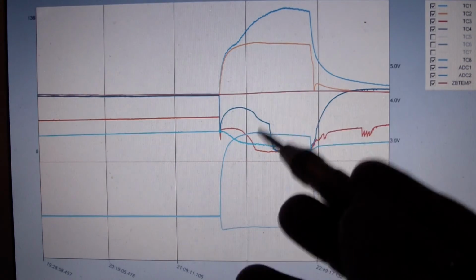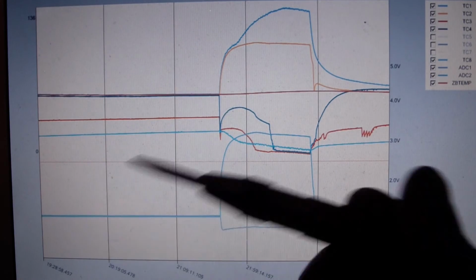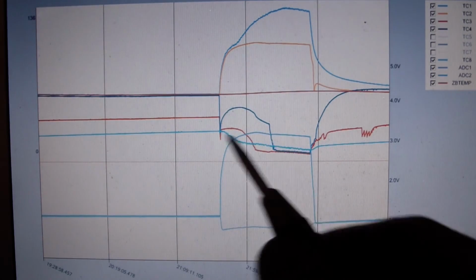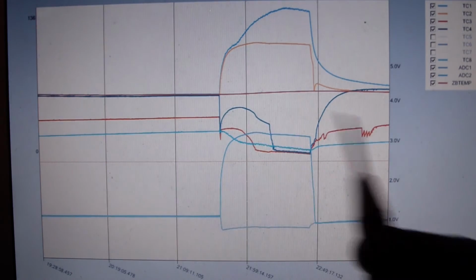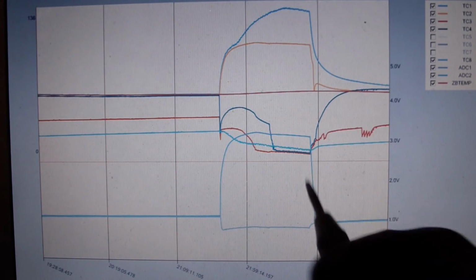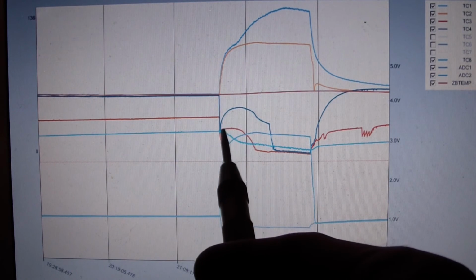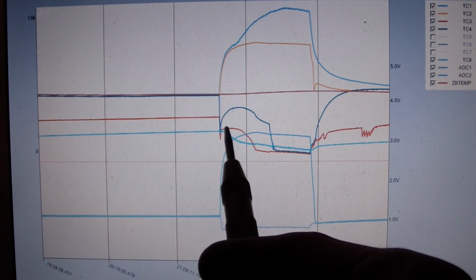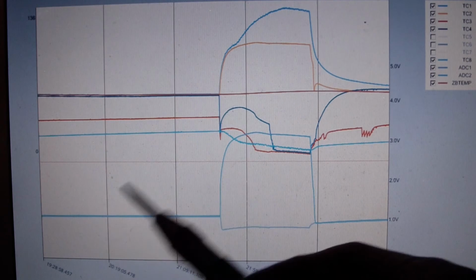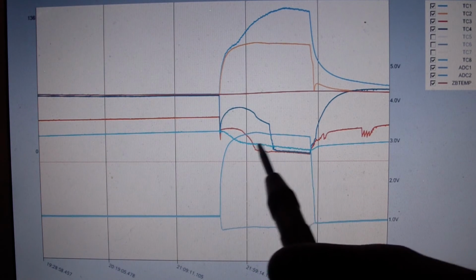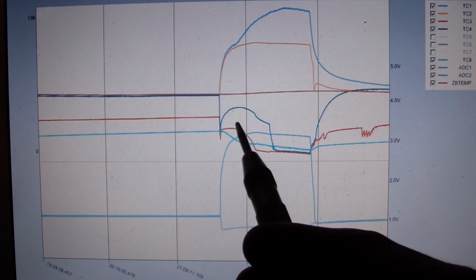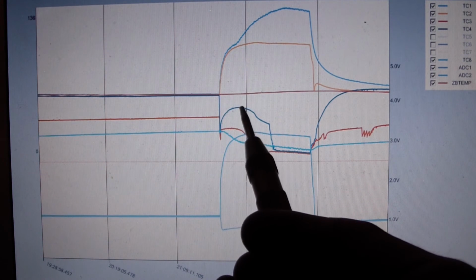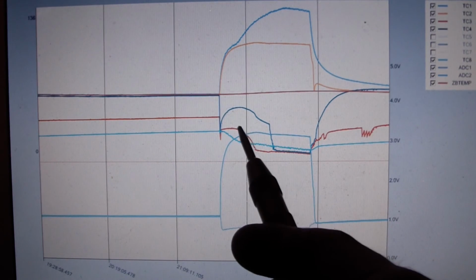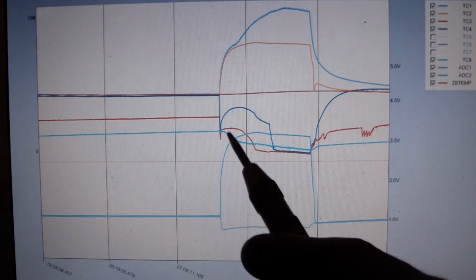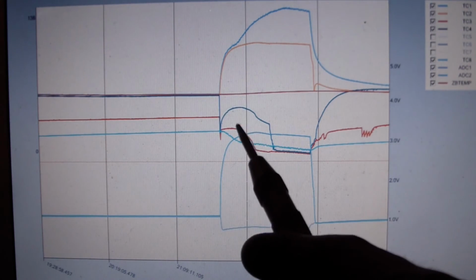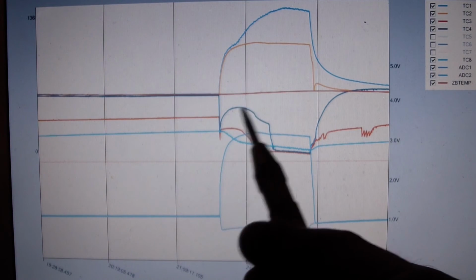In addition to that, I want to get better subcooling on the high side. So I need to add some more heat exchange area there, and possibly a receiver there, and balance these things together. Beyond that, when we first start up here, although we have still pretty high superheats right after the evaporator, this red line, relative to saturation temperature, which is pretty much where that's at right there. You can see that the superheated gas finally going to the intake valve and the compressor is probably that much double in temperature. So it's a very rarefied gas, and that's due to the heat interchanger there and all the heat being added by the capillary tube.